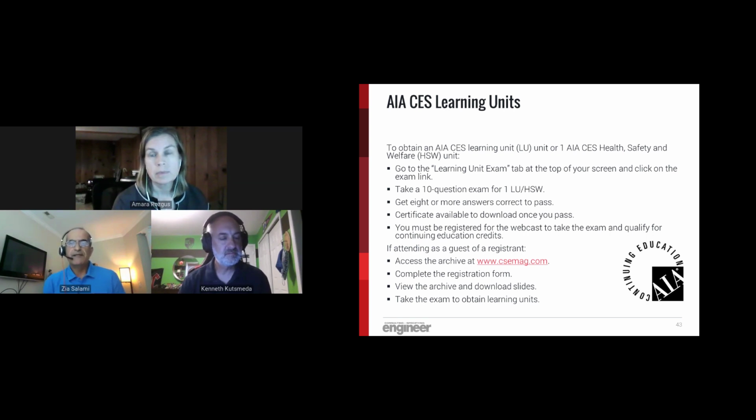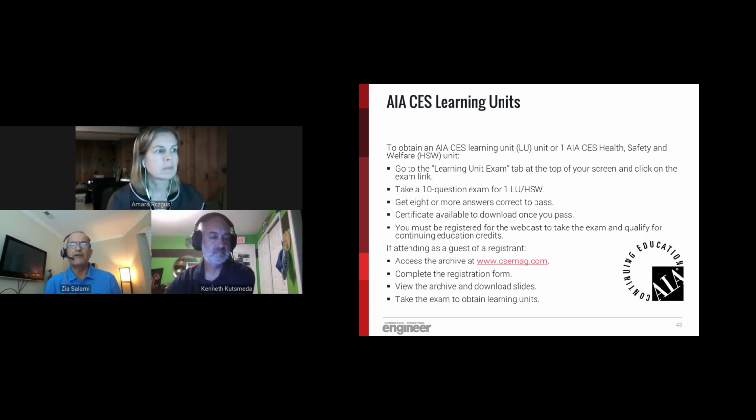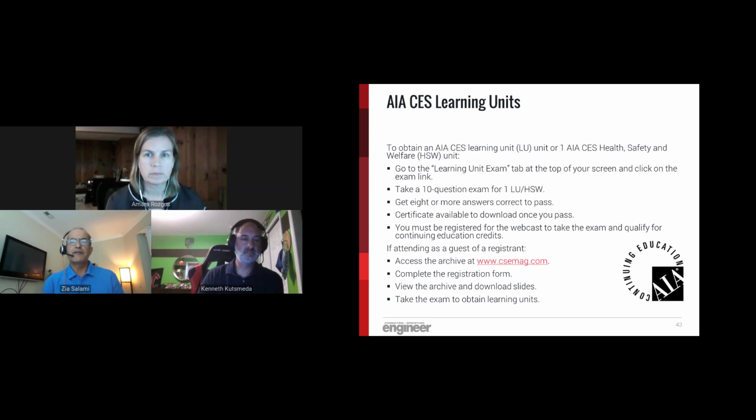Good question, and people do need to actually use those types of fuses. Going back to answer this question, some software such as ETAP have a few approaches to deal with the current limiting fuse. Some software may not have it, as our friend pointed out, like SKM or others. Again, this is my suggestion. Sometimes when the software doesn't have that capability, we have to get around it by creating some cases that achieve our objective.